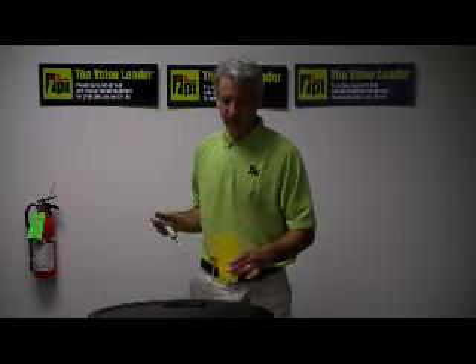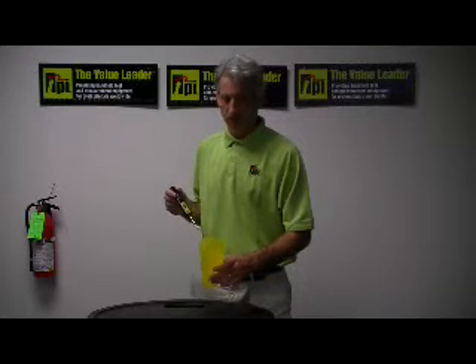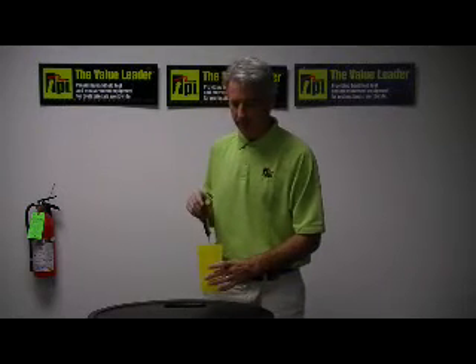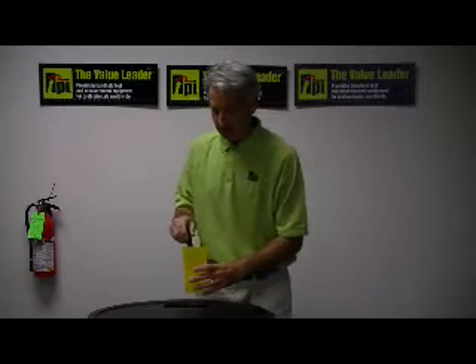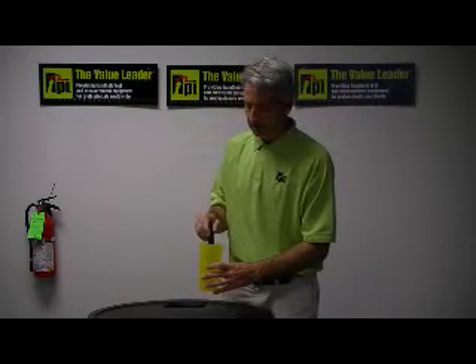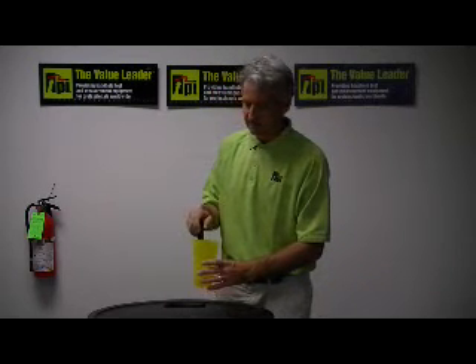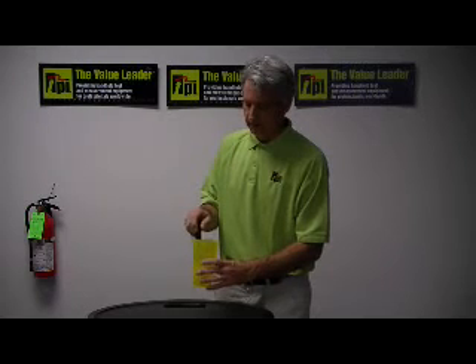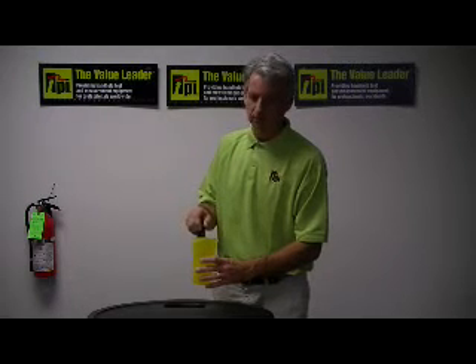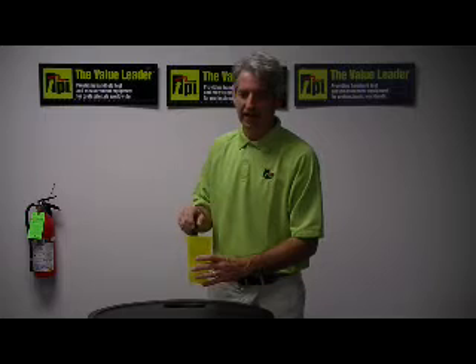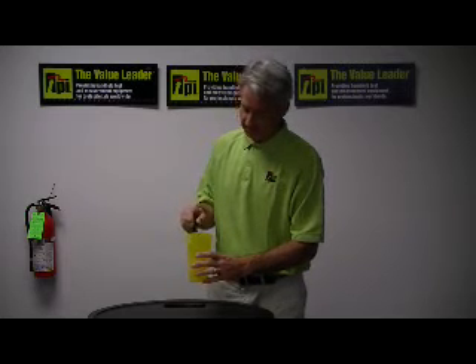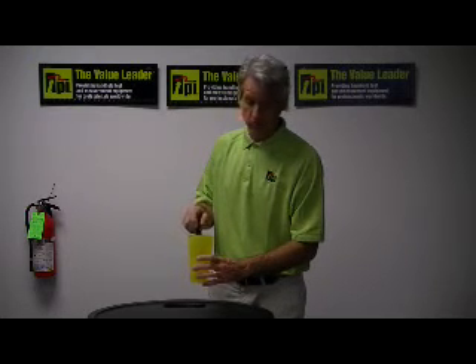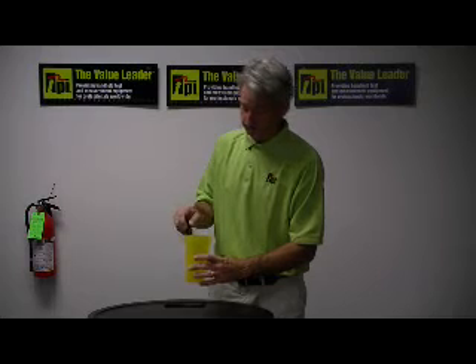So I take some crushed ice and add it to some water inside a metal or plastic cup. I turn on my unit and begin swirling my stem in this ice water solution, making sure that at least a half inch to an inch of the stem is exposed to the water solution.